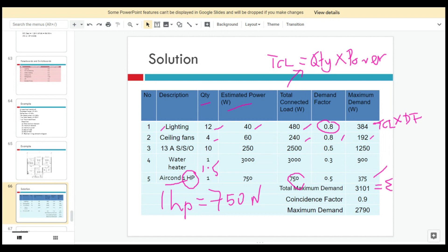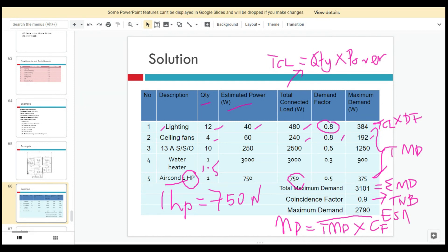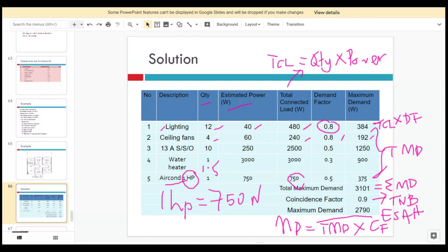The total maximum demand (TMD) is the sum of all individual maximum demands for all electrical appliances. Then the maximum demand for this house is MD equals TMD multiplied by the coincident factor. From the TNB Electricity Supply Application Handbook (ESAH), for residential use the coincident factor is 0.9. So the maximum demand for this house is approximately 2790 watts, which is near 3 kilowatts.